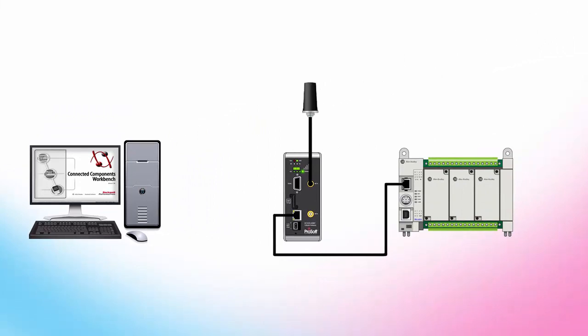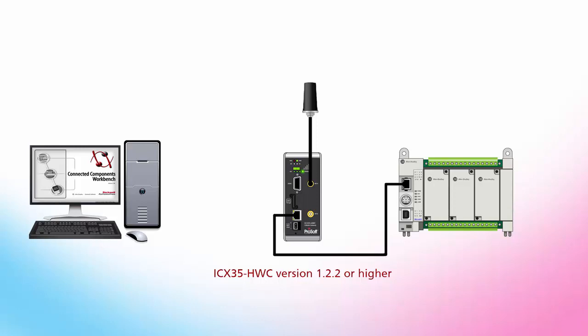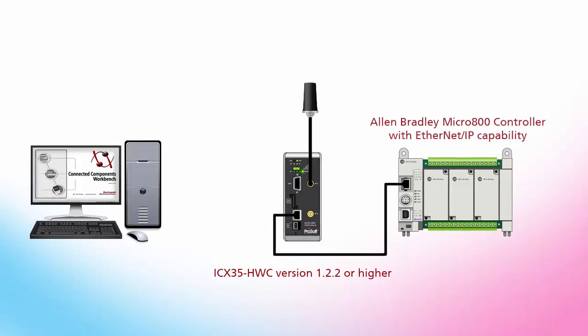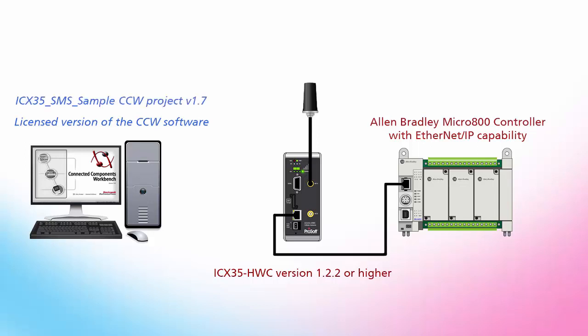Before we begin I'll list the requirements for the configuration. You will need an ICX35 wireless gateway with firmware version 1.2.2 or higher, an Allen Bradley Micro 800 controller with Ethernet IP capability which would be either the Micro 820 or the Micro 850, a licensed version of the CCW software installed on your machine, and finally the ICX35 SMS sample CCW project version 1.7.